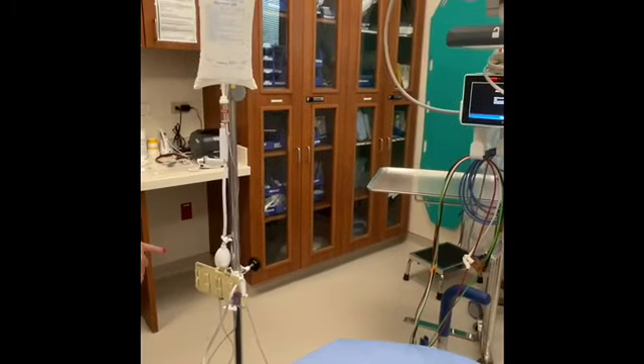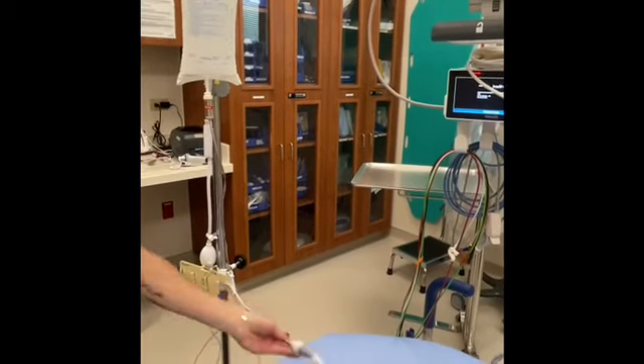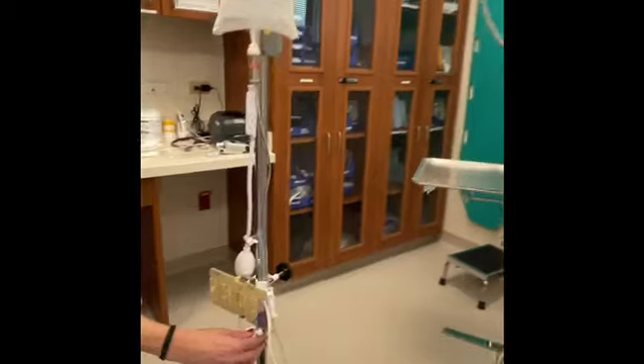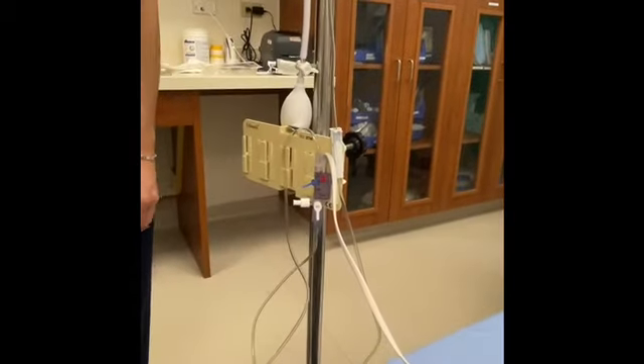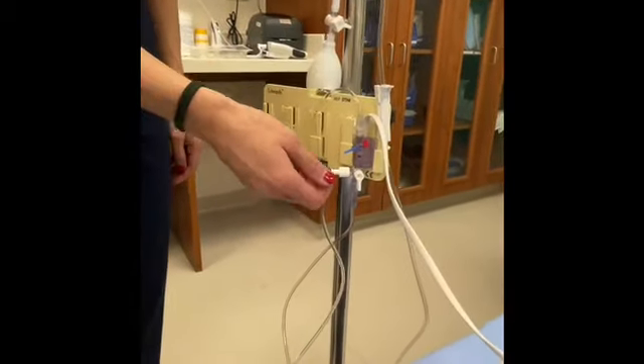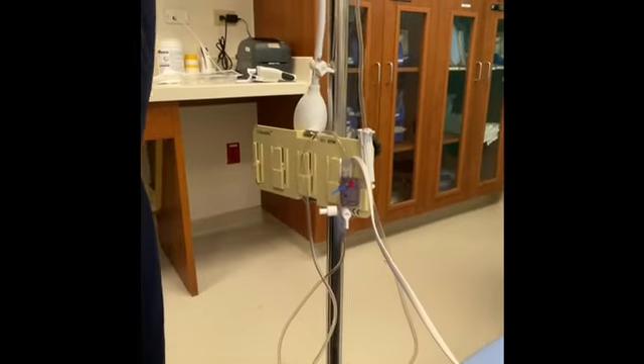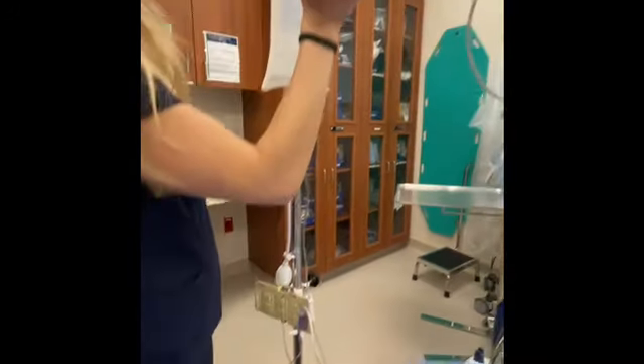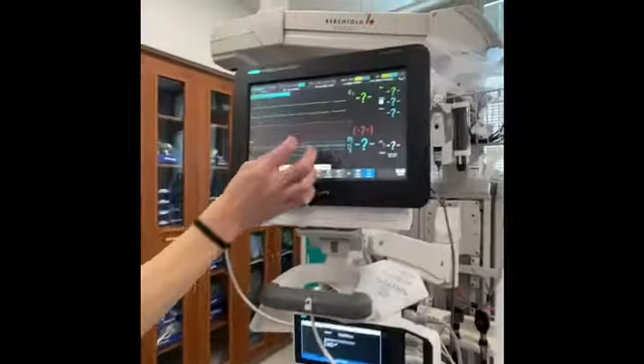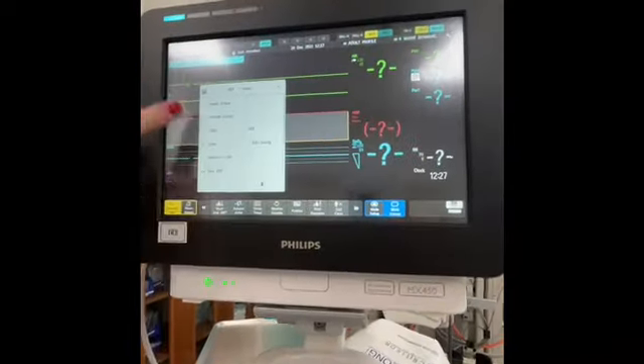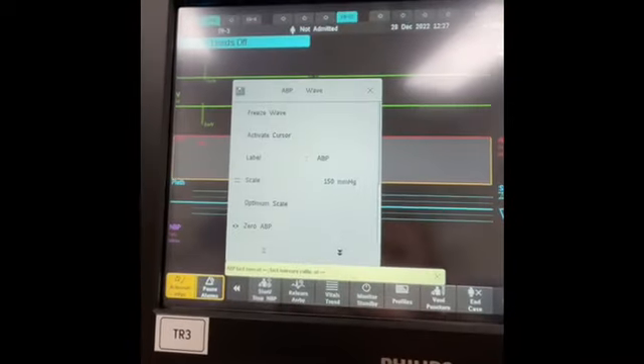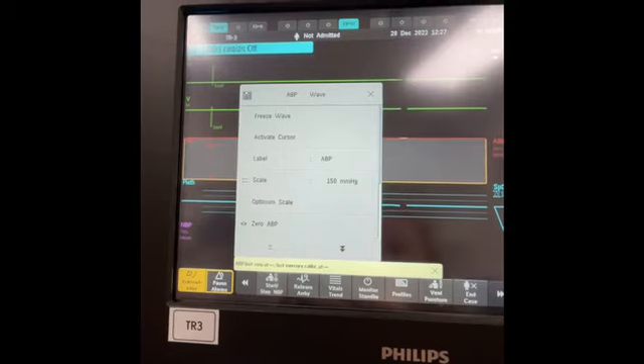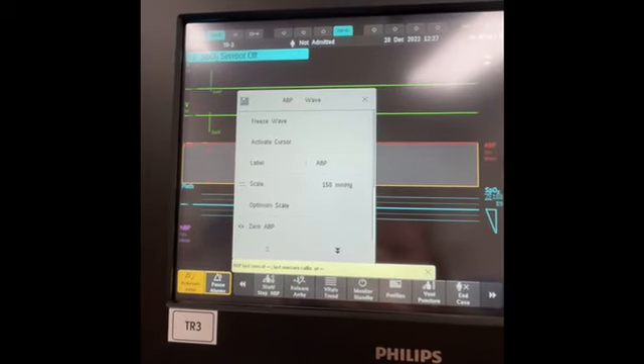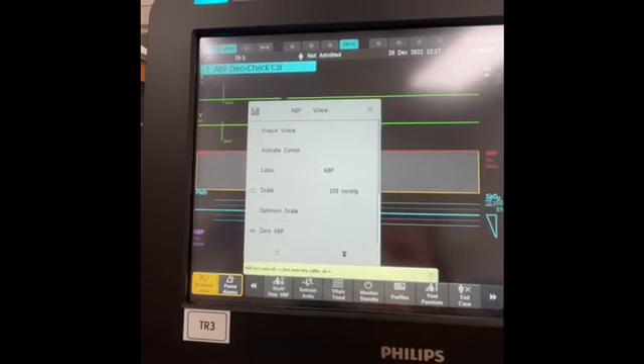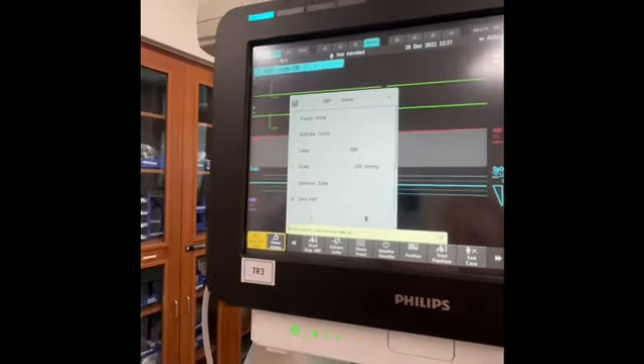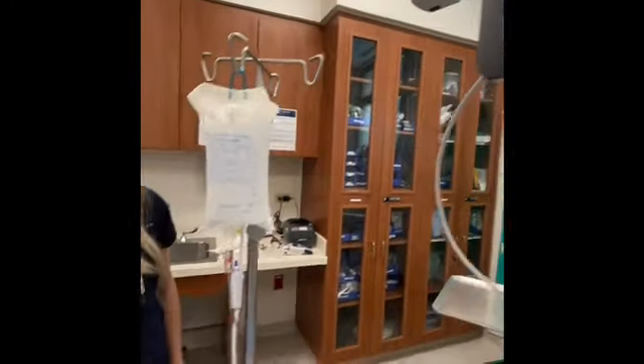Now we're going to go ahead and zero it on the monitor. In order to do this, we're going to shut off the stopcock to the patient, so it's off to the patient. We're going to go to our monitor and click on it here. If you just click on the waveform, you have all these options that come up. So we're going to push the one that says Zero ABP, but we're not going to push that until we actually remove the cap. So we're going to very carefully open this line up to air.